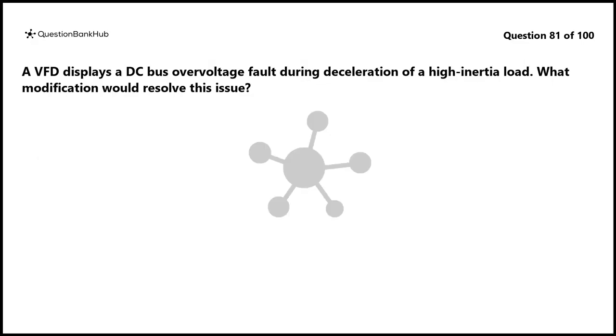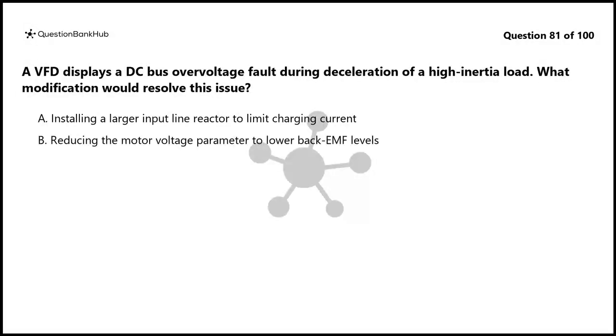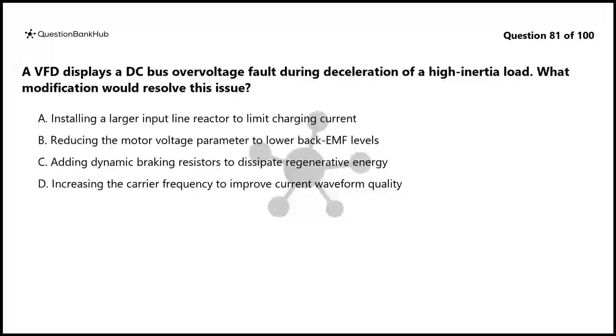Question 81. A VFD displays a DC bus overvoltage fault during deceleration of a high inertia load. What modification would resolve this issue? A. Installing a larger input line reactor to limit charging current. B. Reducing the motor voltage parameter to lower back EMF levels. C. Adding dynamic braking resistors to dissipate regenerative energy. D. Increasing the carrier frequency to improve current waveform quality.